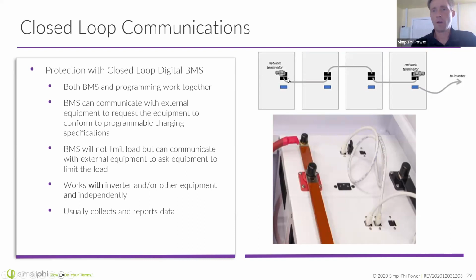They're daisy chained together essentially with Cat5 cables. So you're essentially just going to run a communication cable from the battery port on one battery module to the next battery port on the next battery module. Same thing for that second battery to the third and the third to the fourth. No battery modules should have an empty plug. If there is an empty port because there's no battery to the left of battery number 1, you should put a terminating resistor here. And that terminating resistor allows the batteries to know that is the end of the CAN bus chain, right? There's nothing to be communicating there. And I think it's just a 100 ohm resistor. Daniel, do you know for sure, is that just a 100 ohm resistor inside that network terminator? Yeah, I'm not sure the value, but it's a resistor.